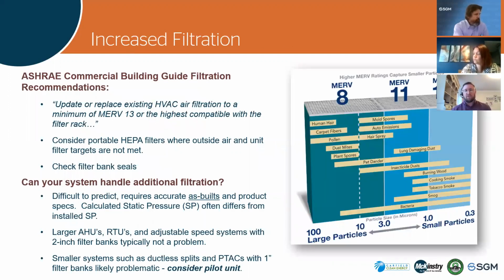Next major recommendation is increased filtration. So ASHRAE's recommendation is MERV 13 minimum, and also look at HEPA filtration where it's possible. Most existing systems are not going to accommodate a HEPA filter unless they're specifically designed for that initially. So MERV 13, moving into say 14 and 15, if you think your system can handle it. And then we want to also make sure you're checking the filter bank seals on this.